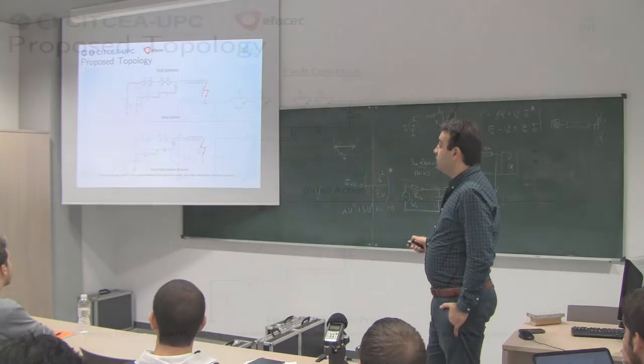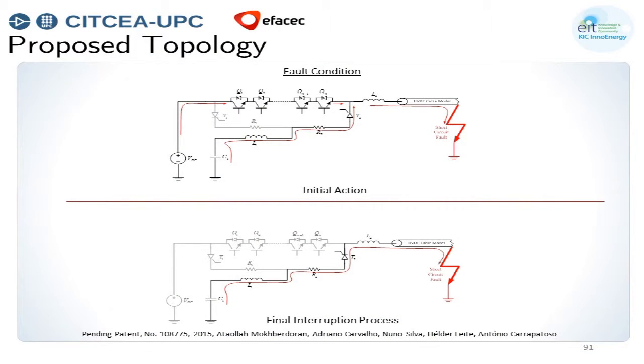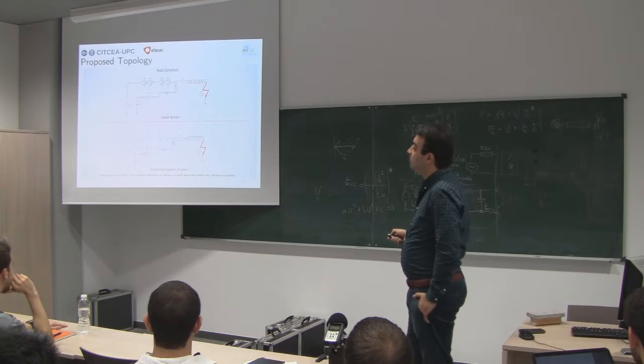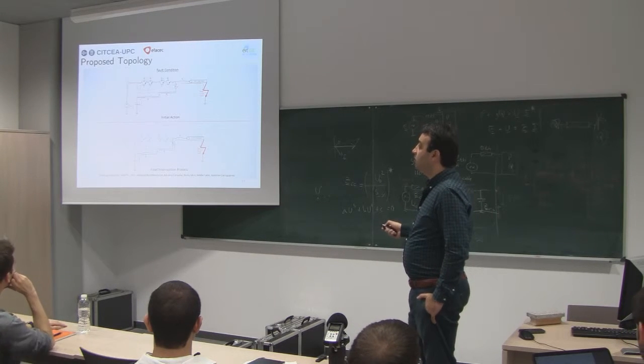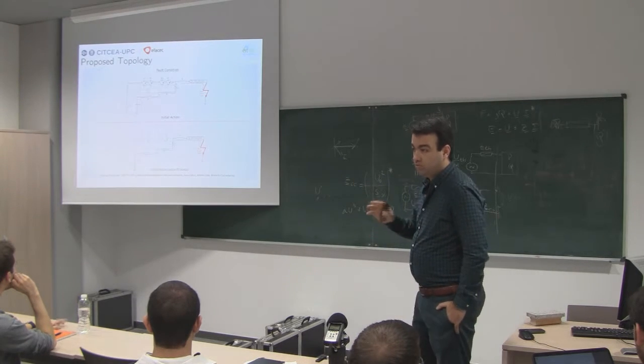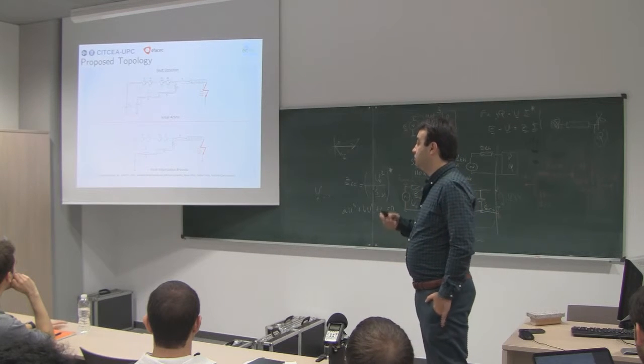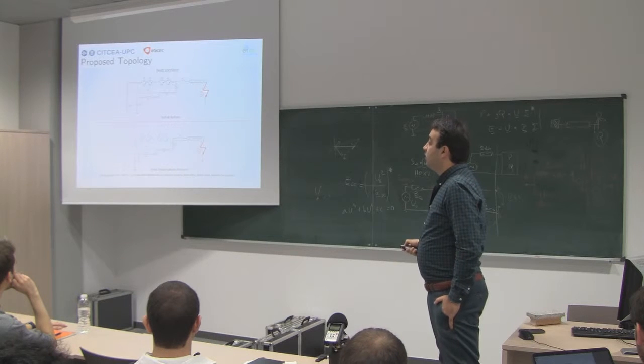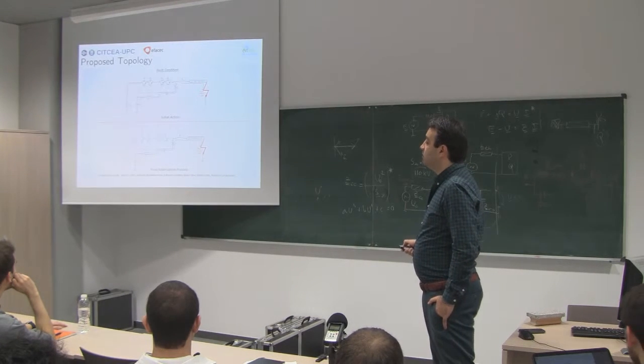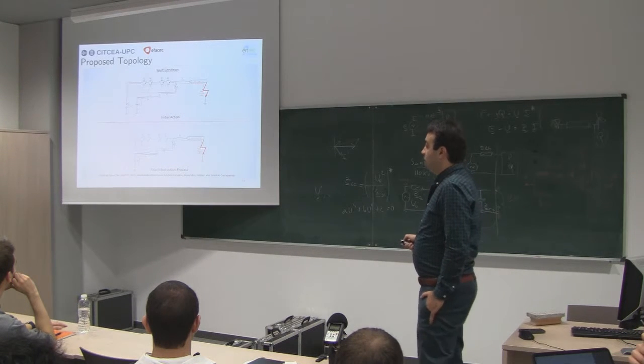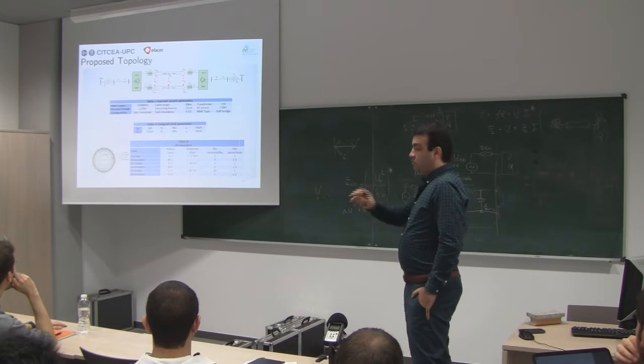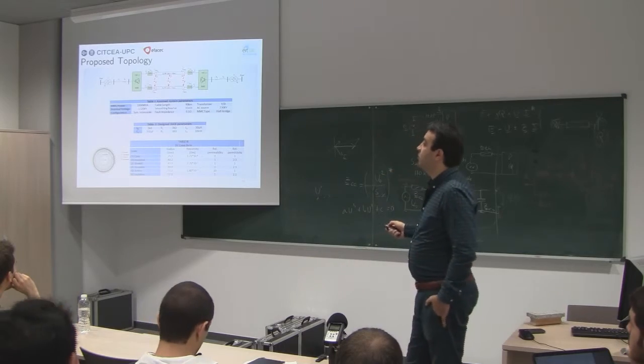So during the fault, what we are doing is triggering this thyristor, which is connected to this pre-charged capacitor, at the nominal voltage of the grid. So we have some kind of nominal voltage which is connected to this point, and it will prevent the voltage of this point from dropping because of the interruption that we are going to do, and because of these inductors, the inductor of the cable and this fault limiting inductor. And then we will open these IGBTs very smoothly without very, very high surge voltage. So the IGBTs and the breaking device will be safe. And after a while, the current through this capacitor will discharge to the fault point, and this thyristor will be turned off naturally.